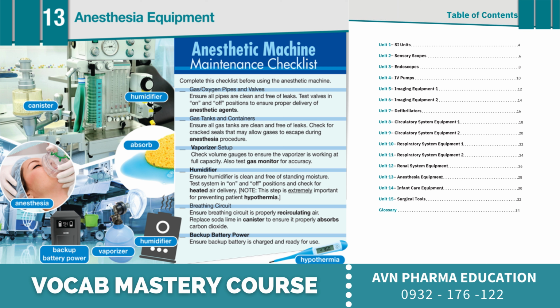Vaporizer setup. Check volume gauges to ensure the vaporizer is working at full capacity. Also test gas monitor for accuracy. Humidifier. Ensure humidifier is clean and free of standing moisture. Test system in on and off positions and check for heated air delivery. Note: this step is extremely important for preventing patient hypothermia. Breathing circuit. Ensure breathing circuit is properly recirculating air. Replace soda lime in canister to ensure it properly absorbs carbon dioxide. Backup battery power. Ensure backup battery is charged and ready for use.